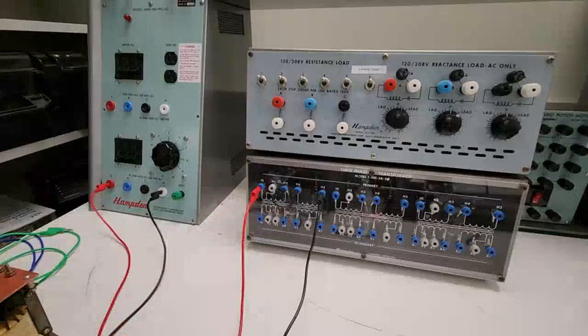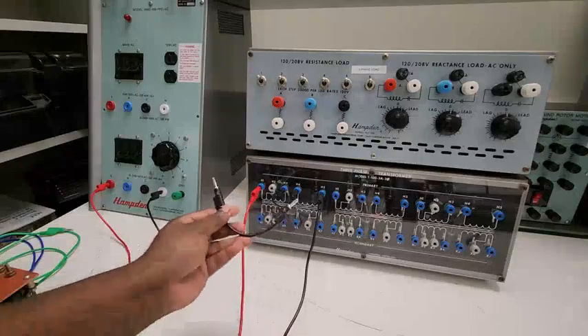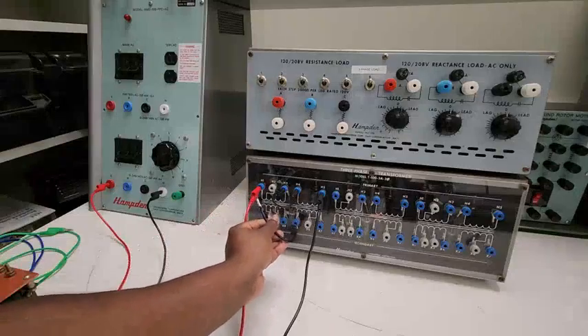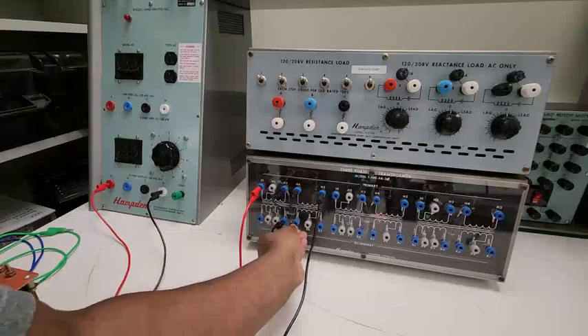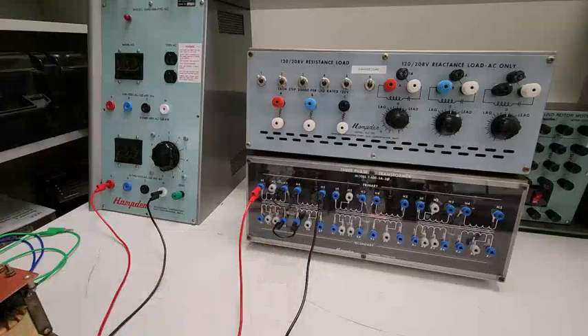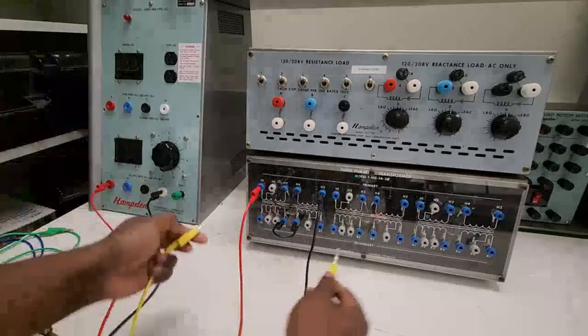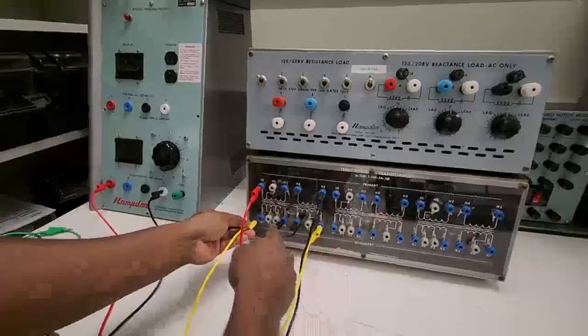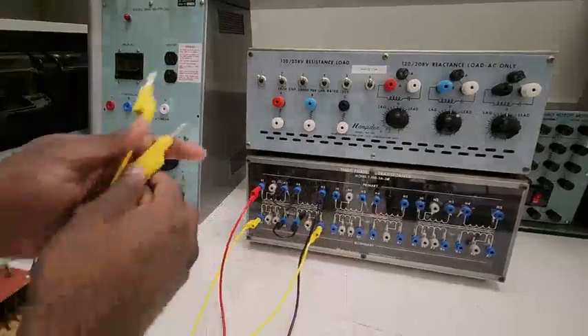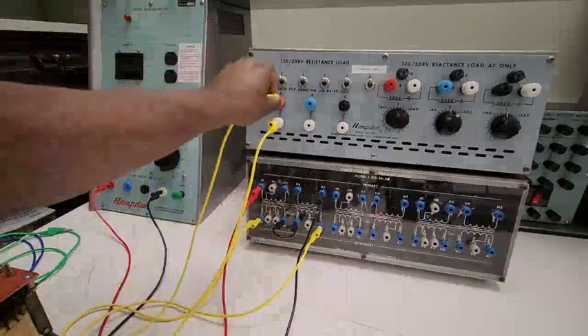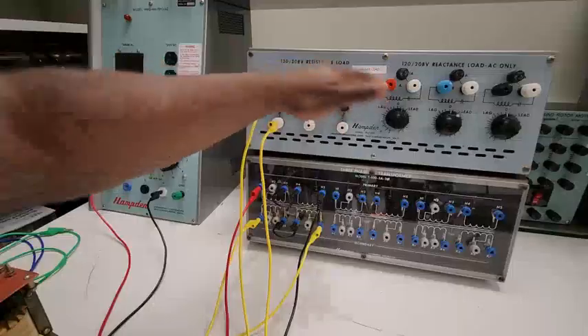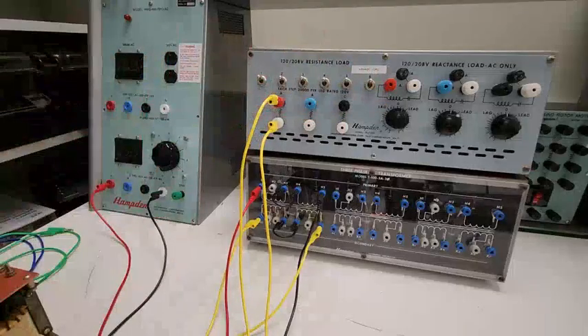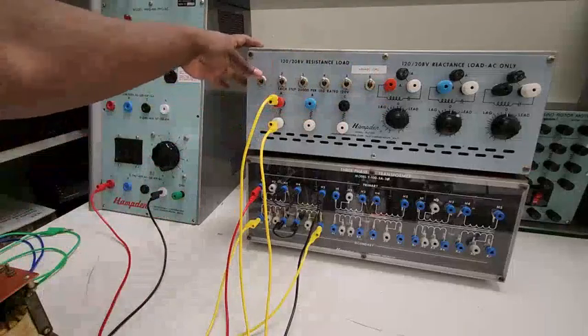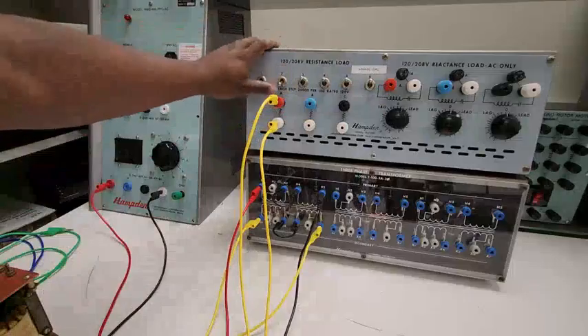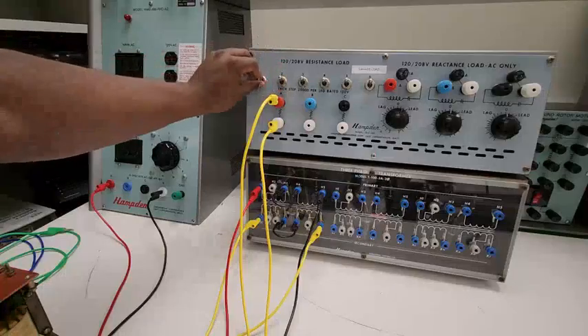For the secondary side we need a short banana cable like this. We'll connect this to this jack, and connect the secondaries X1 to X7, meaning the whole winding, to one of the loads — we could use A, B, or C. I choose to use B. We can change the value of resistance like this, or use one of them.